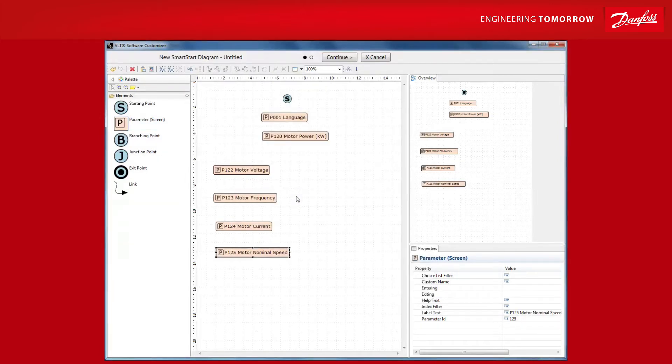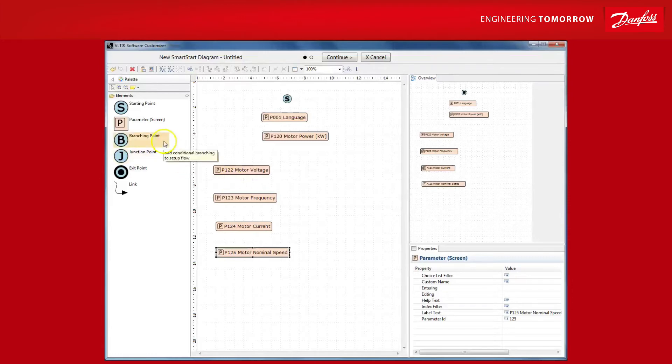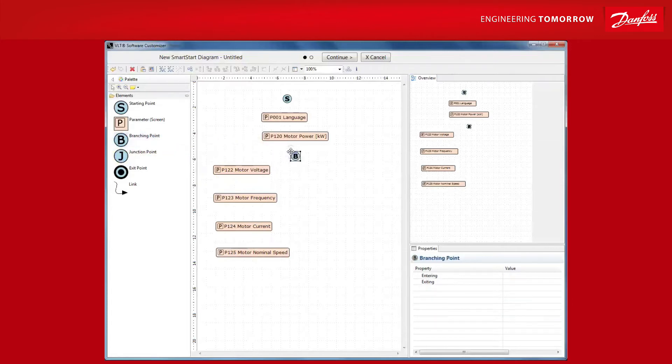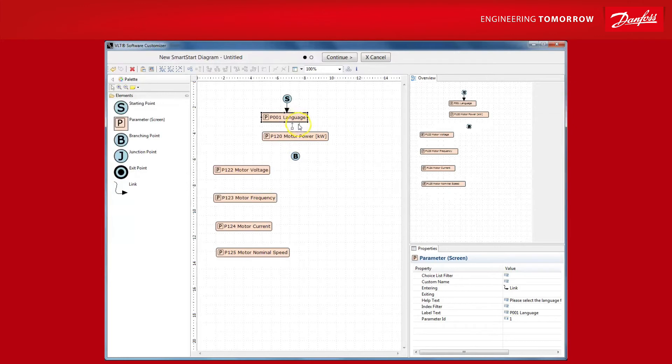Now, for our example, let's assume we commonly use a particular 3kW motor. So, in case the drive will be commissioned with this motor, we will have the smart start wizard automatically input the relevant motor data and not prompt the user for all of these. To do this, simply select a branch point and let's start connecting the elements. Grab the link tool from the elements toolbox and start connecting them. You can also just hover over an element and use the shortcut to link them together.